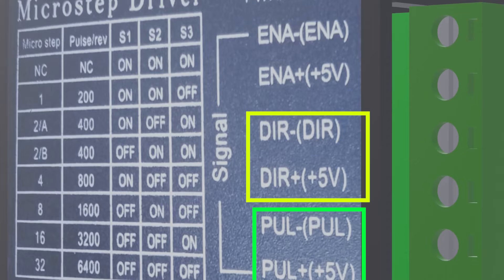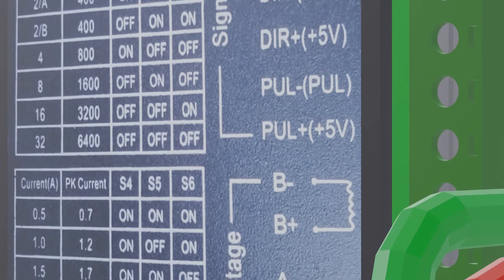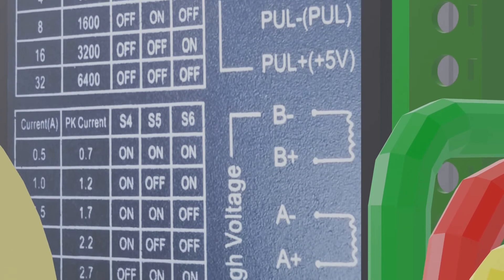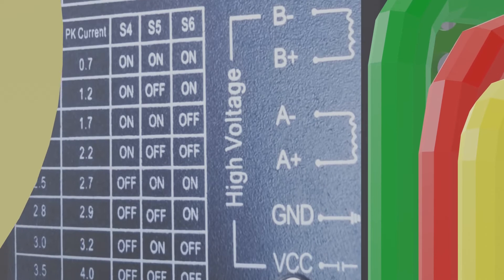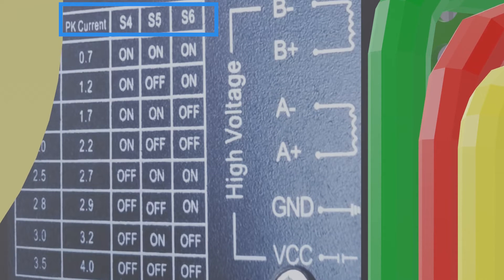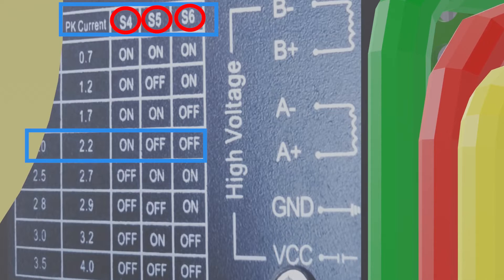The negative direction and negative pulse connect to the respective outputs of the PLC with a resistor. Now we will see the configuration of the amperage of the motor. We have the current on switches 4, 5, and 6, which we are going to configure for 2 amps, of which we will activate only switch 4.